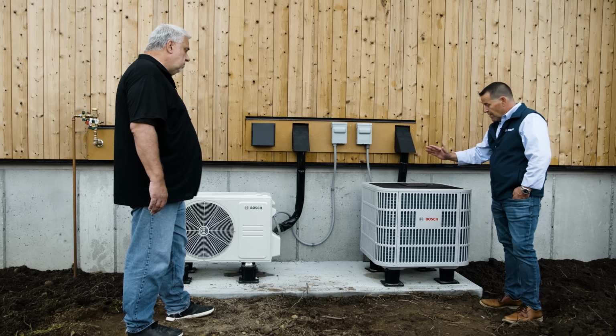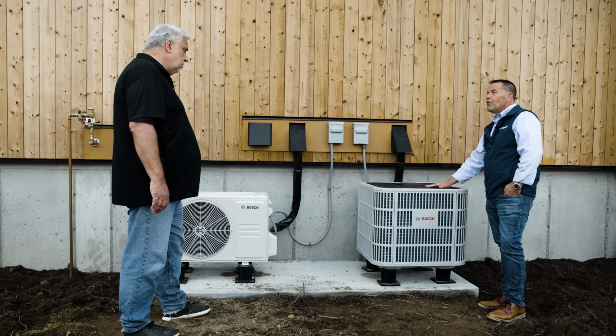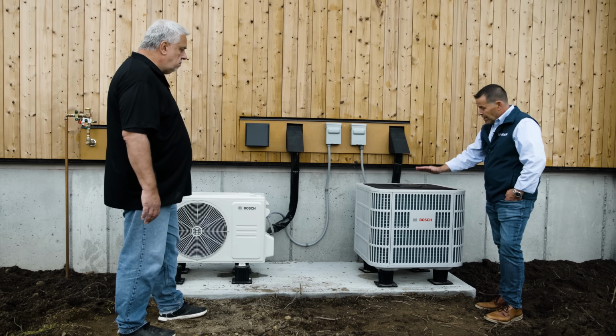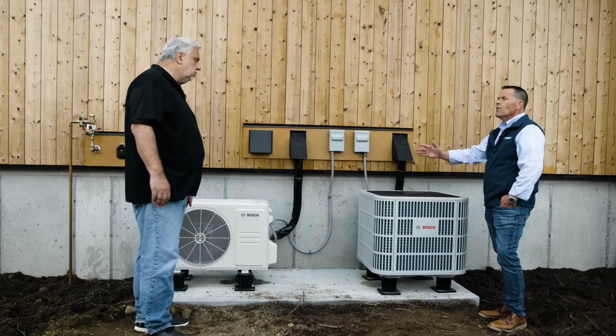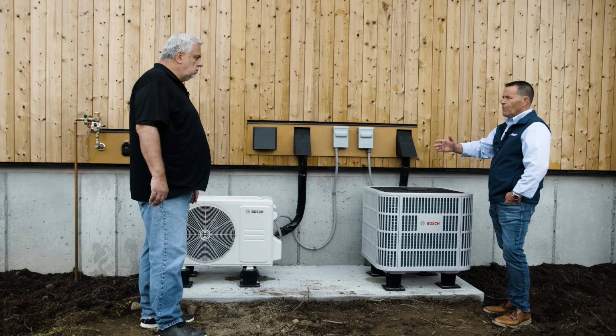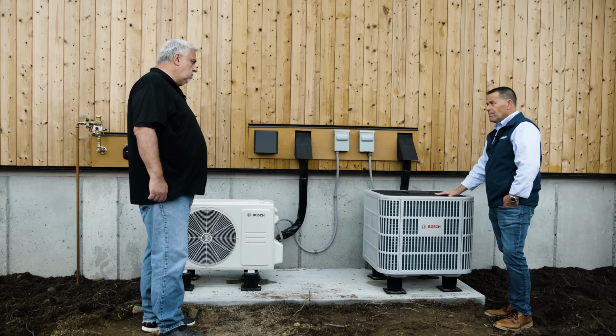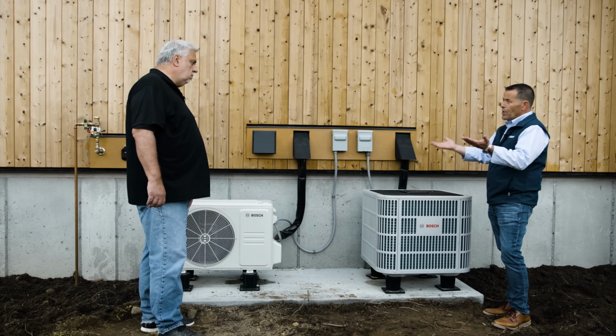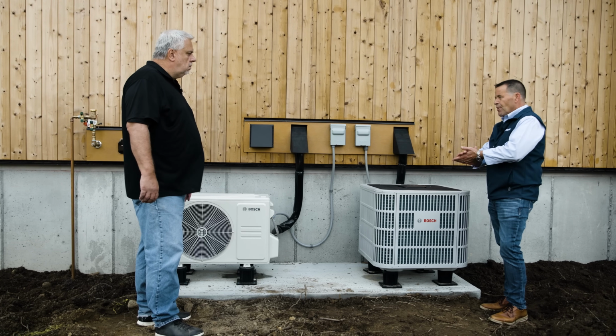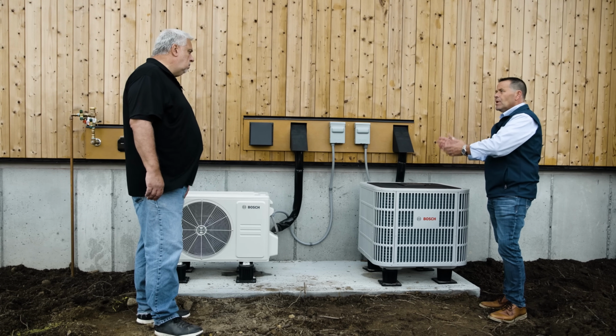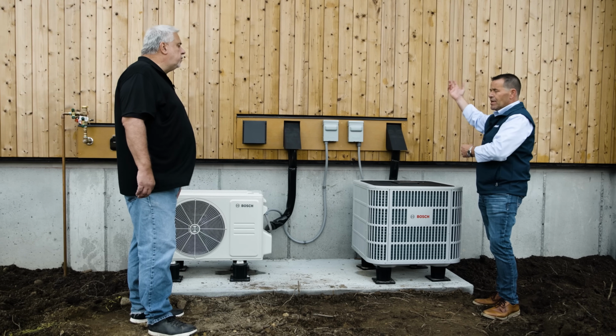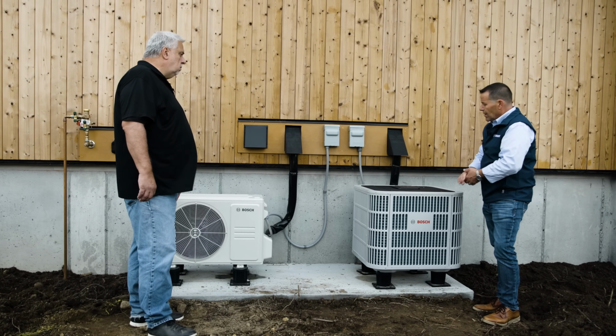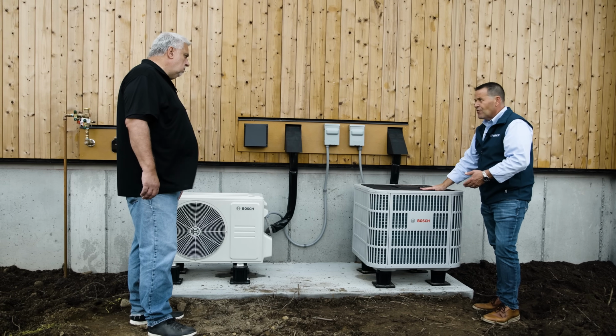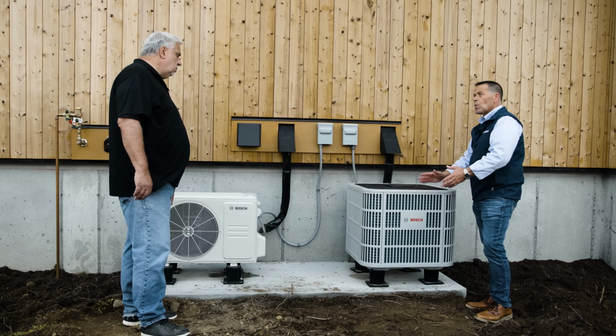If a homeowner already has a furnace in their house, we can connect this heat pump and do a dual fuel system, so if they wanted to keep their fossil fuel, they could add the heat pump to it. If they're going straight heat pump, we put an air handler in, like in this application, just an air handler upstairs. So if somebody has ductwork, it's not a lot to upgrade to a heat pump.